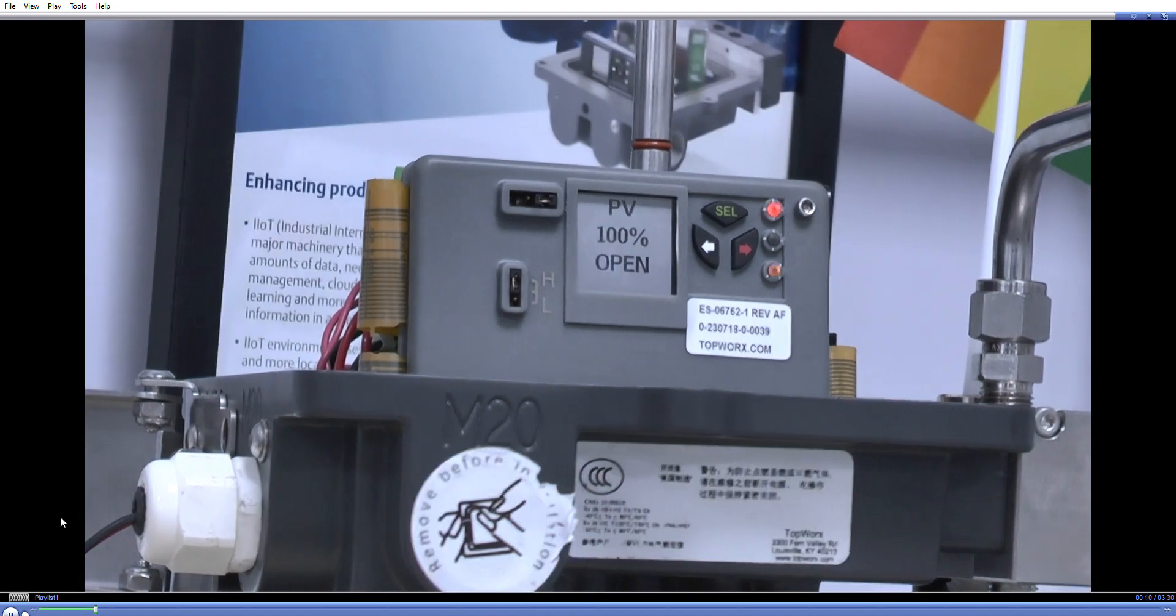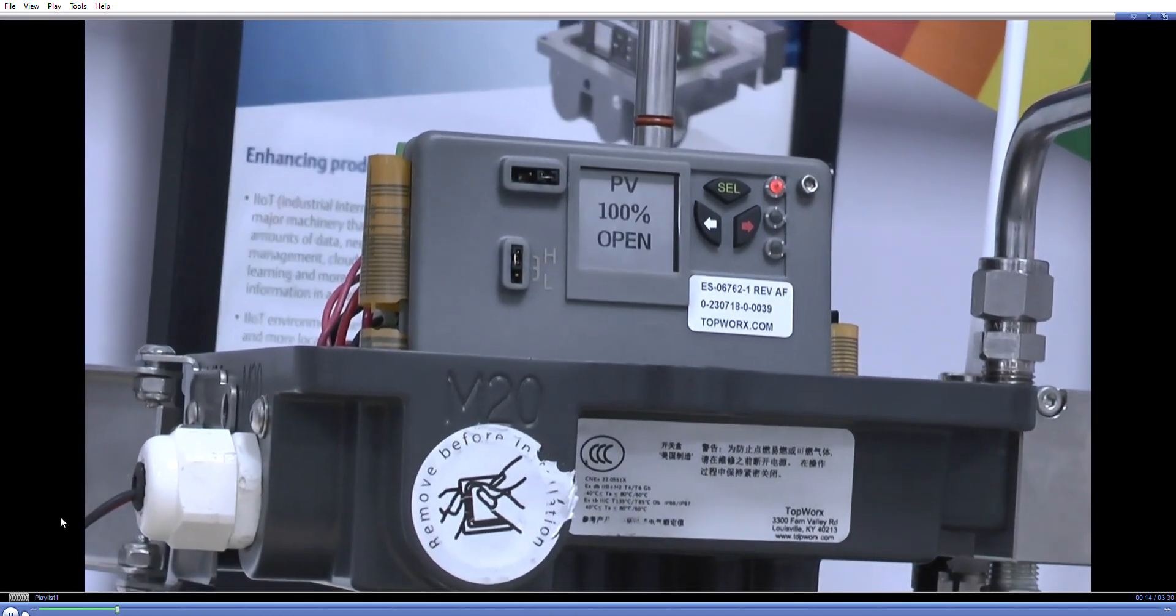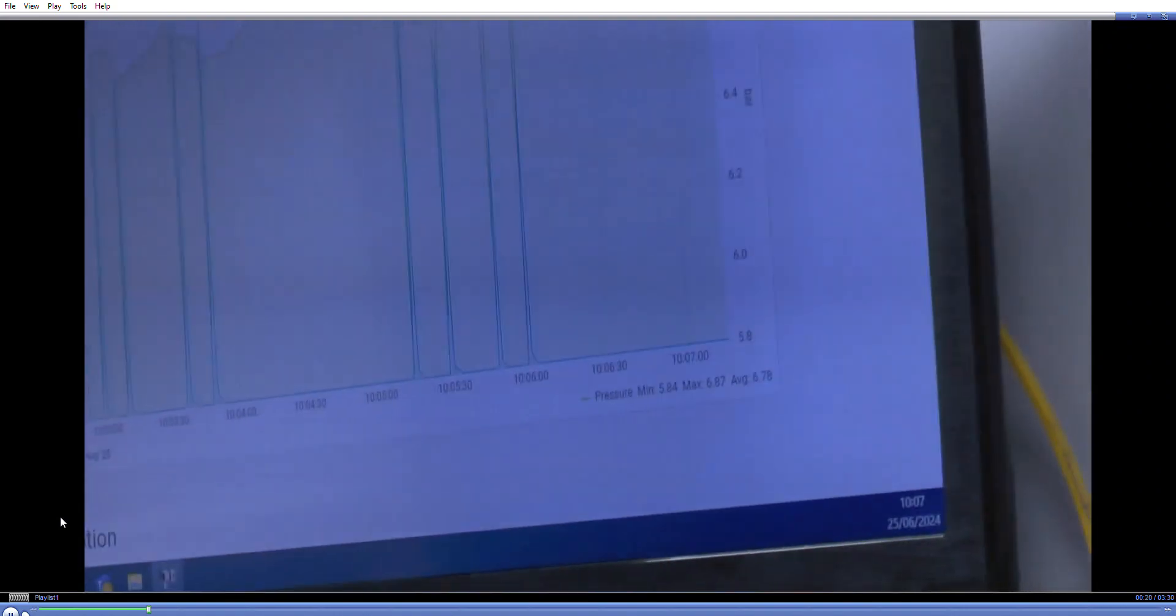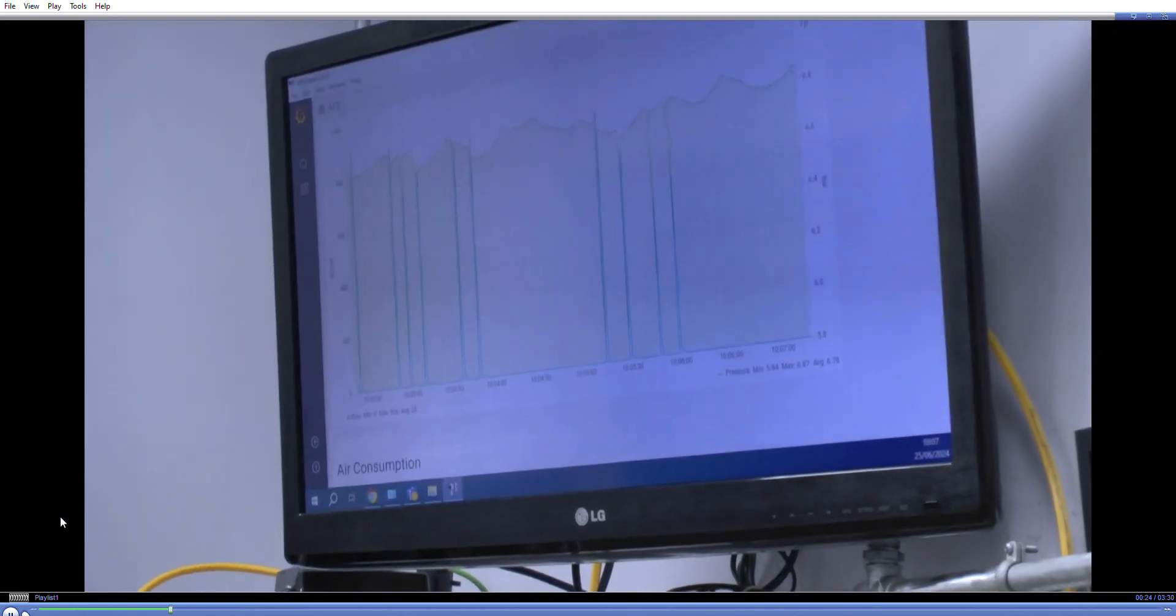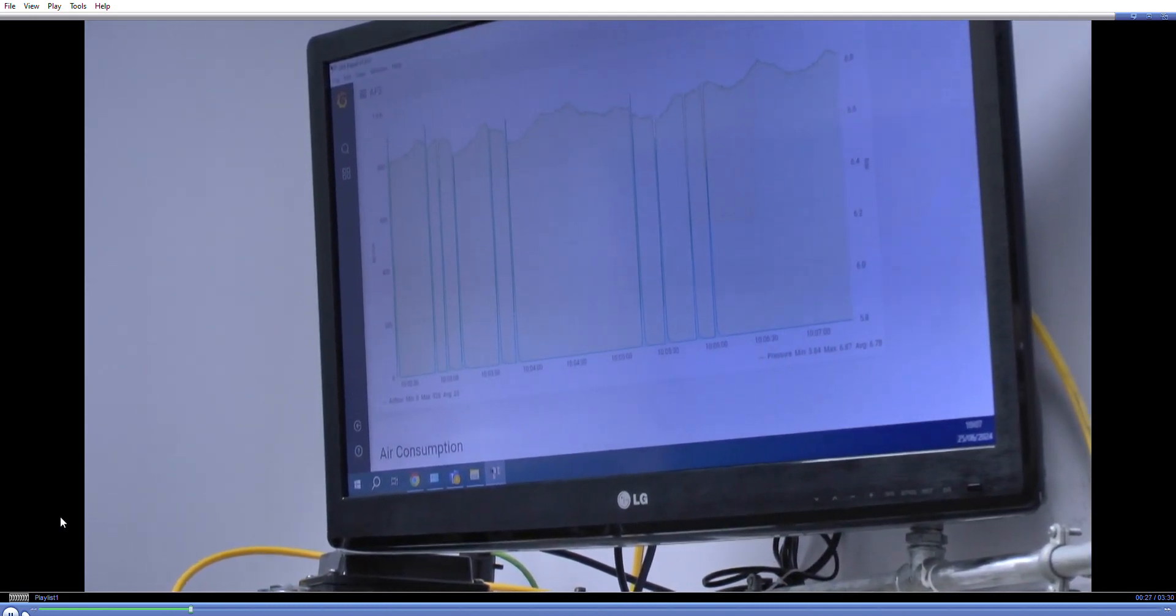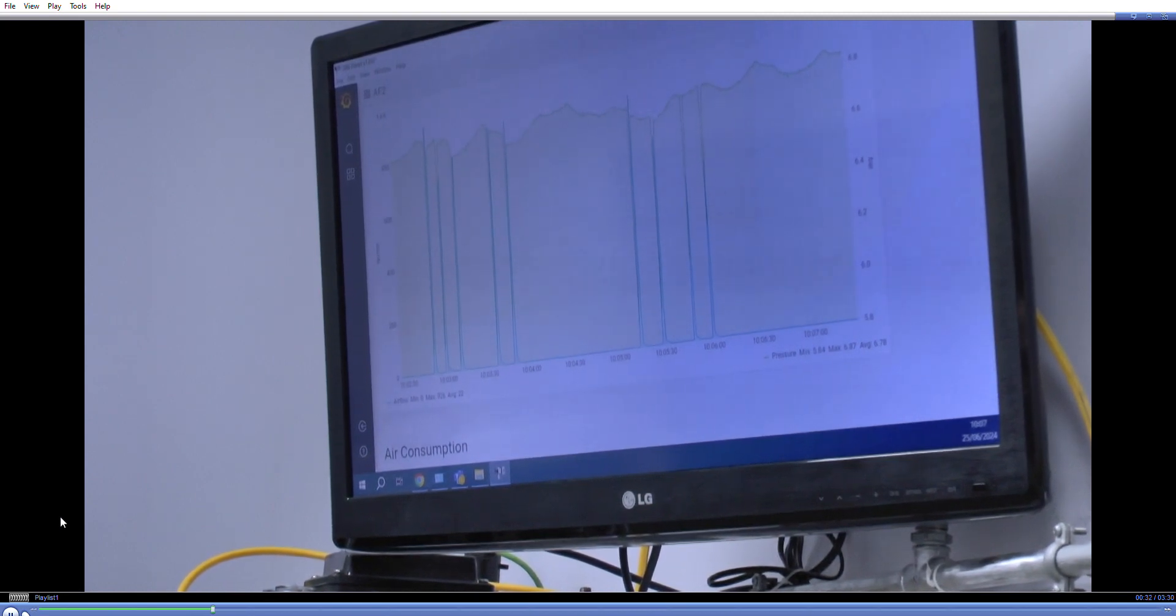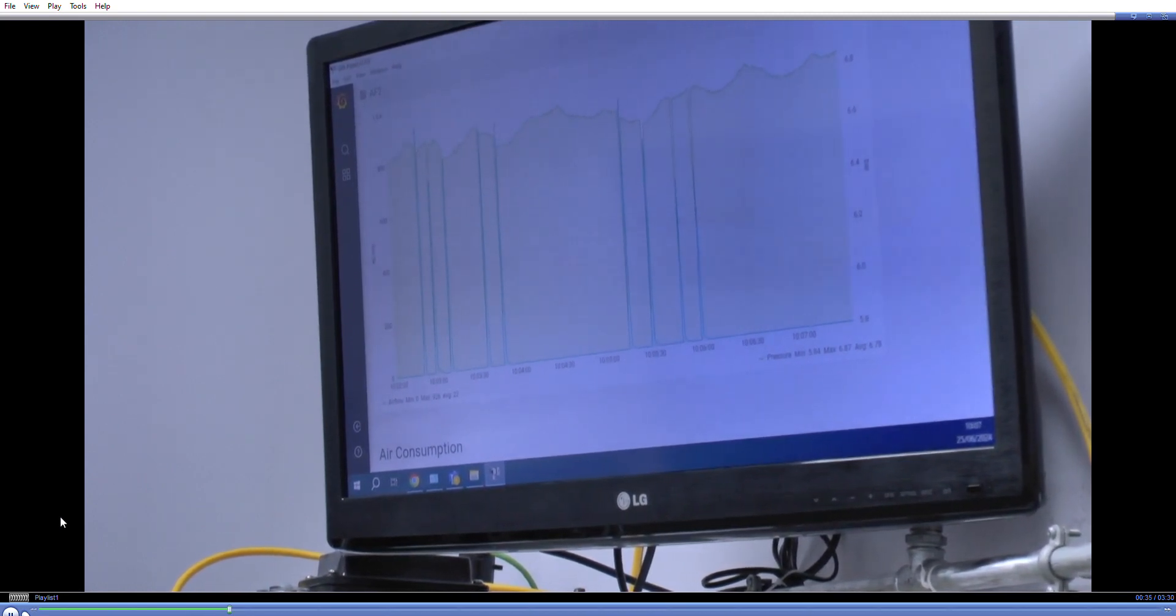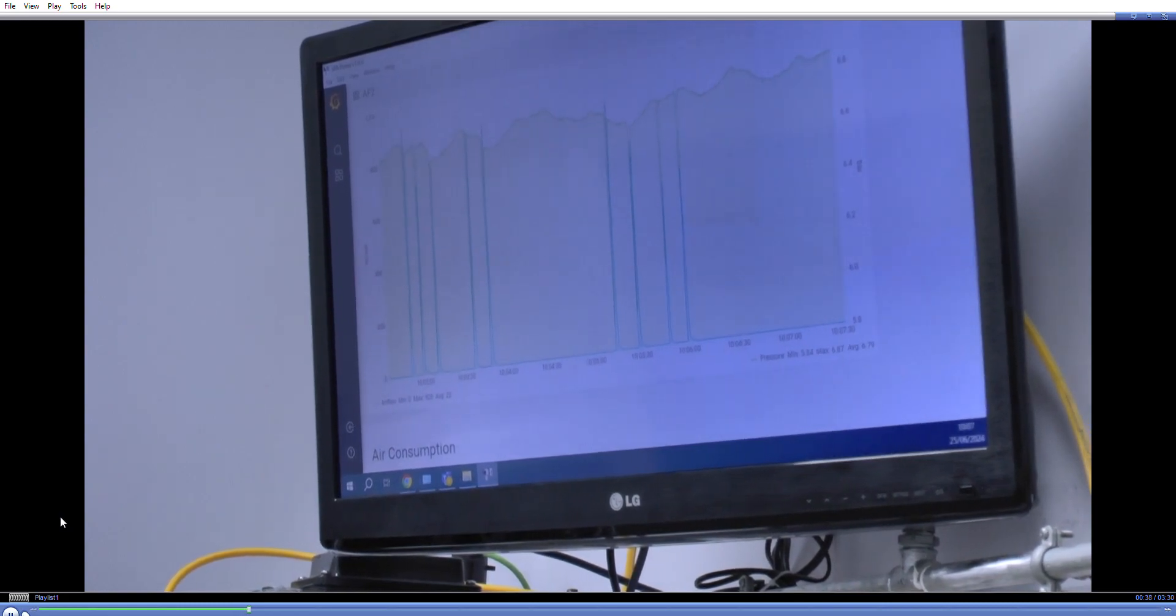At the same time what I will demonstrate is that with our system we also have the ability to measure electronically, as you can see here, the pressure. So we've just performed the test and there are the results using our AF2 flow sensor. We're able to measure in real time and as well as getting a footprint from the device, in conjunction with the AF2 we can get some more diagnostic data.